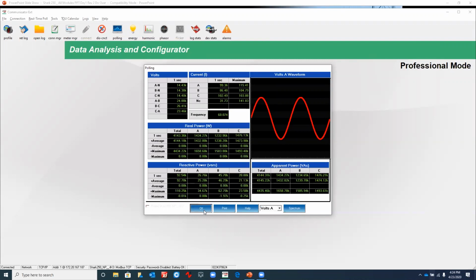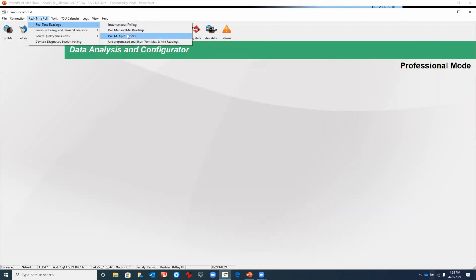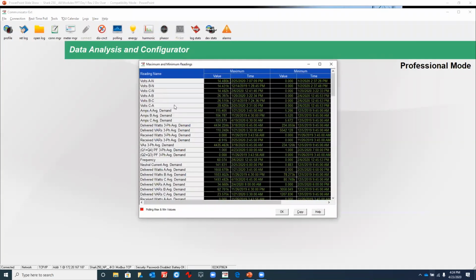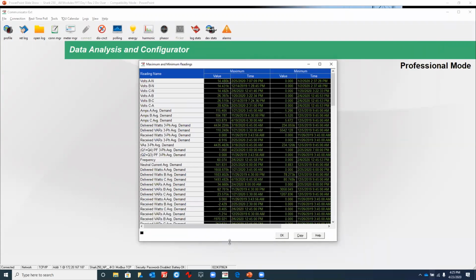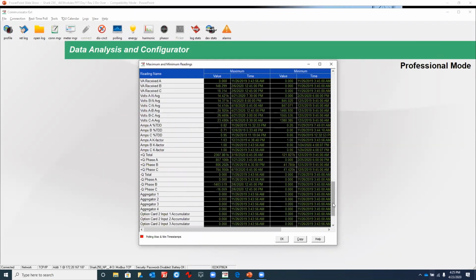So we'll close this out, and we'll take a look at the next screen, which is real-time poll min and max values. So here we can see max and min readings from this screen. VAN, VBN, these are maximum values over a certain period that the file was created for. So we have volts, VAN, VBN, VCN, and phase-to-phase voltage, average demand, maximum three-phase watts demand. So that's the peak value that occurred during this period. There's a date and time associated with that. There is all the other information that you can see with frequency, quadrant, individual quadrant. So you get a large amount of information. If I just expand this further, it almost seems like it goes on indefinitely, but it's just a large volume of data that you get with this min and max screen.